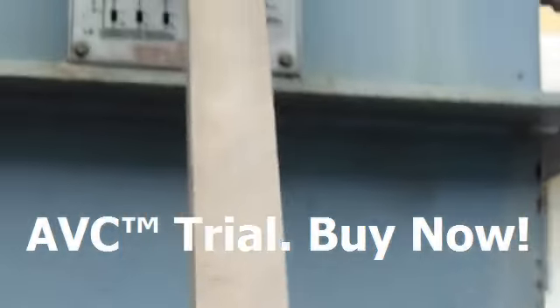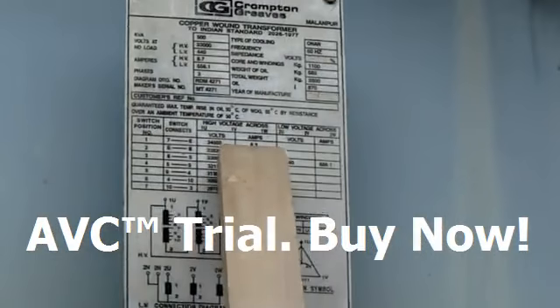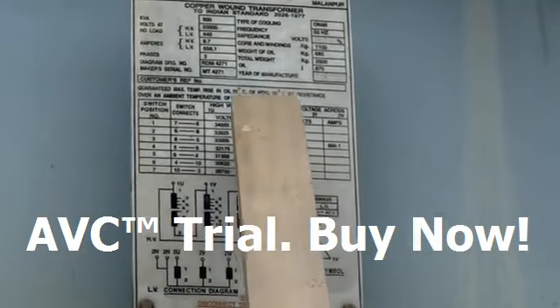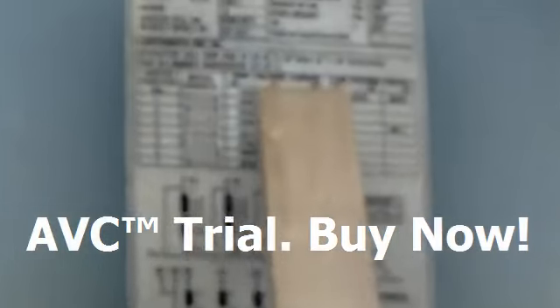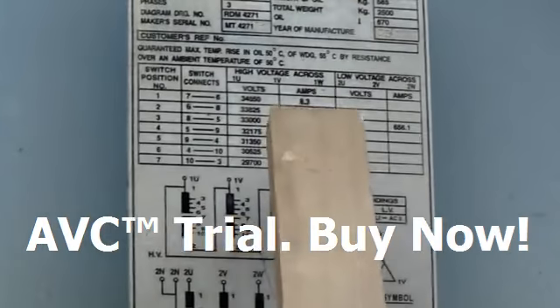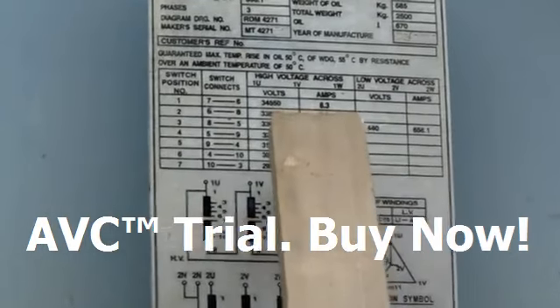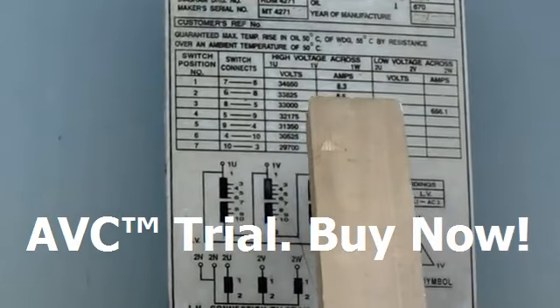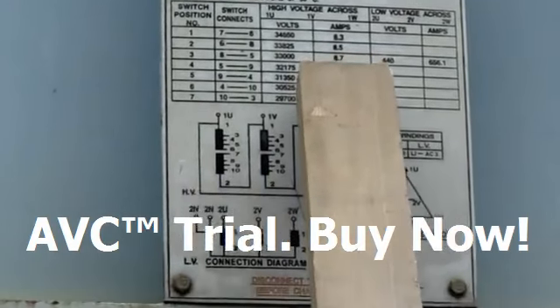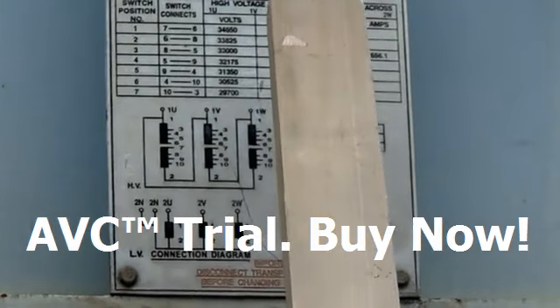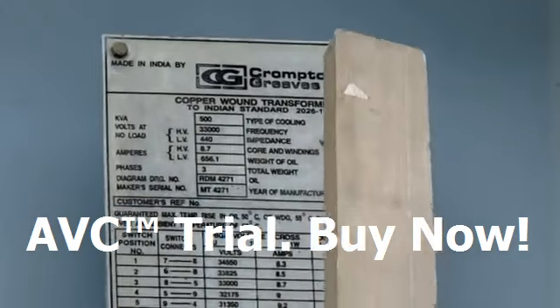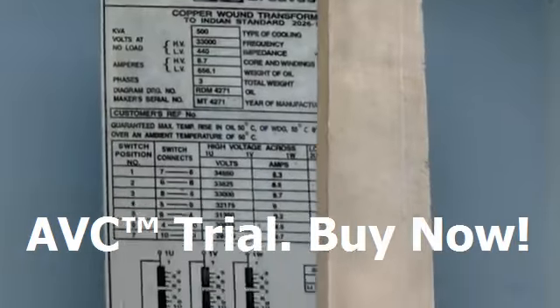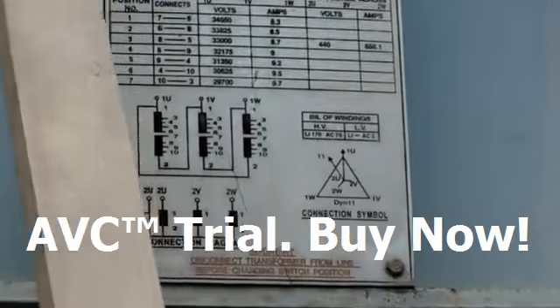The switch position 3 is the nominal voltage rating, that is 33 kV, and 1 is plus 5%, 2 is plus 2.5%, then comes 4, that is minus 2.5%, then 5, that is minus 5%.